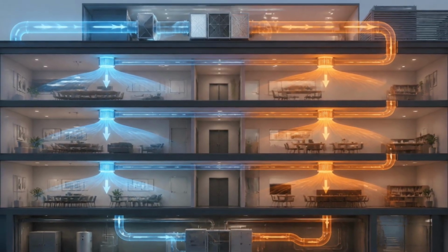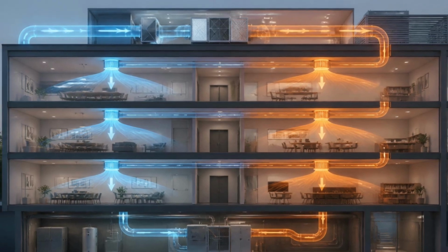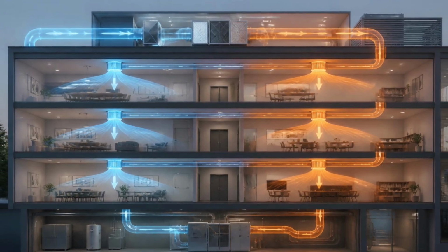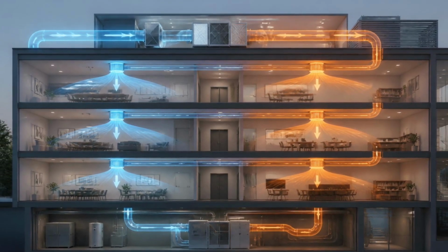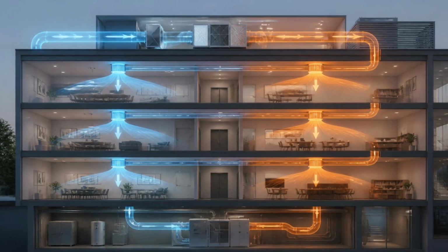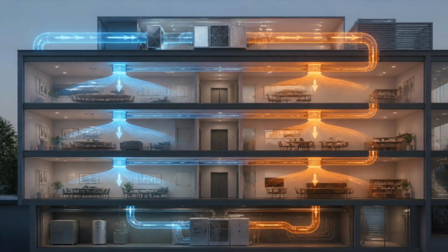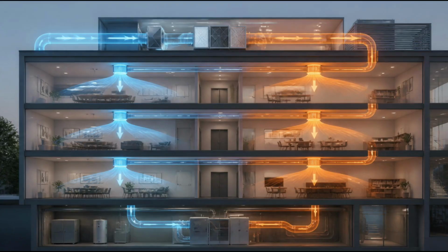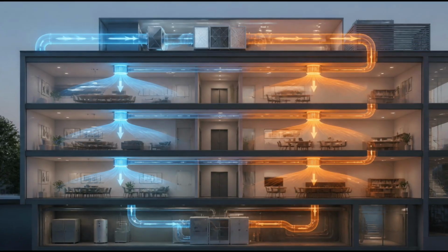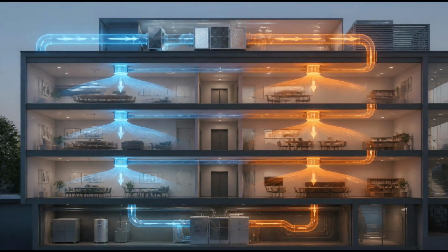The reduction in airflow has several benefits. Energy consumption drops, often significantly, since fans and compressors are the largest power consumers in the HVAC system. Equipment wear is reduced during the hours of lighter operation, and the building itself remains in a condition of gentle, continuous care rather than complete dormancy.